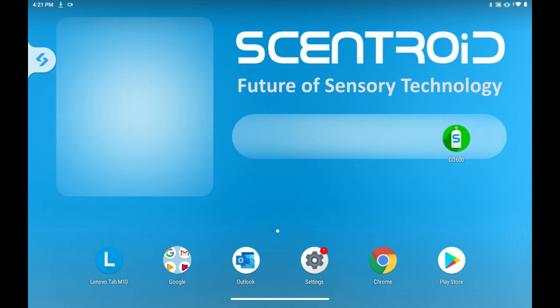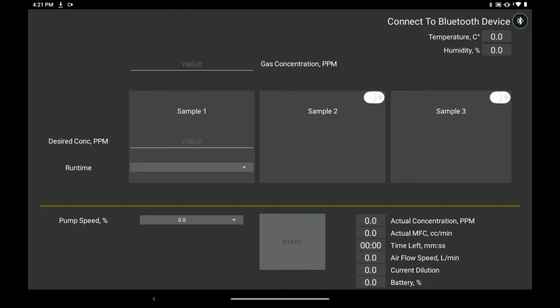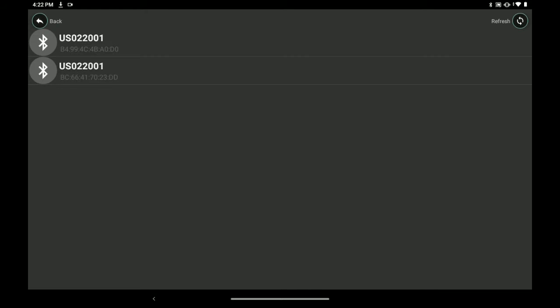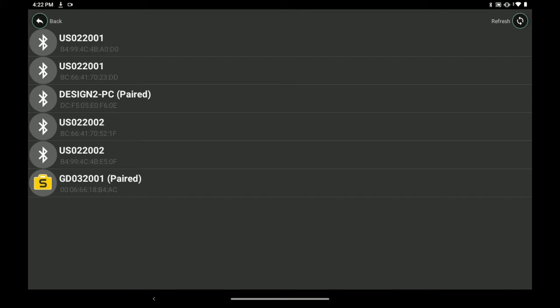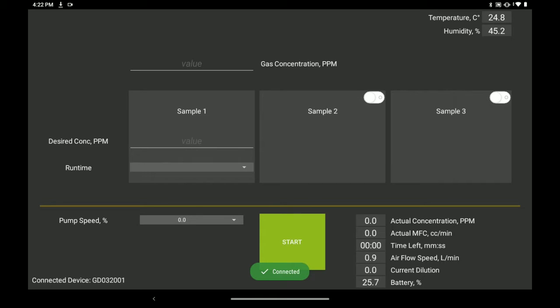Okay, so I've turned on my Android tablet, and the first thing I'm going to want to do is open the GD600 app. Once I have the app open, the first thing you're going to want to do is connect to the Bluetooth device. Once you press on that, it'll start loading all the Bluetooth devices nearby. Once you see your GD600, it'll be the one with the GD600 logo. Press on that. Now that we're connected, you're going to want to check to make sure that the battery is charged enough to perform a calibration. So we're at 25%. That should be enough for our 2 sensors.